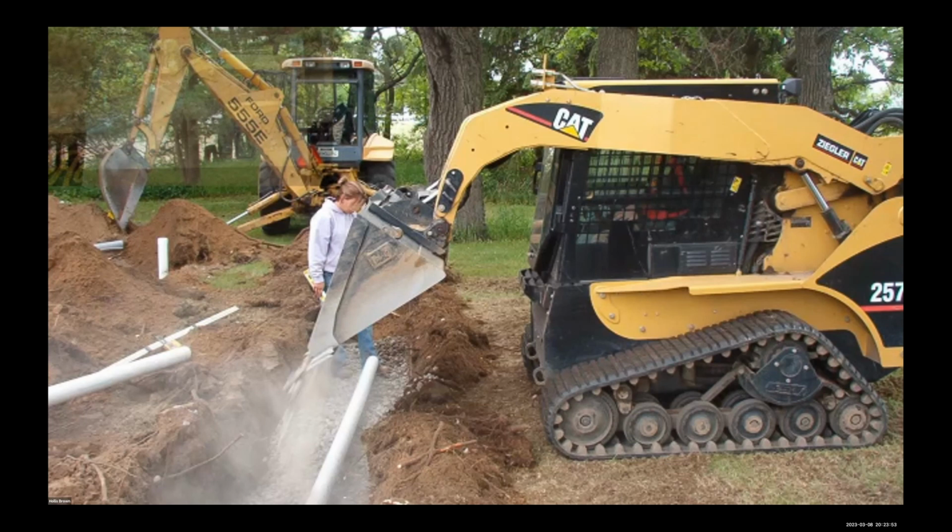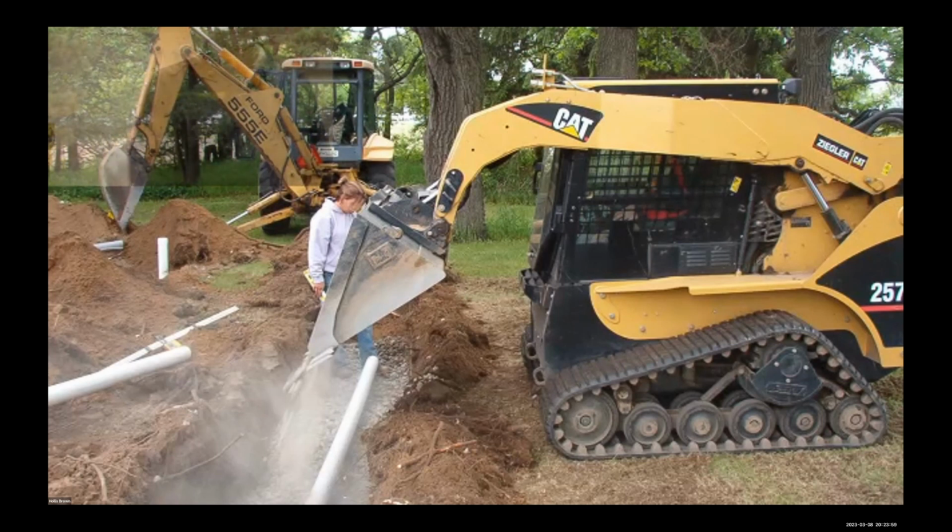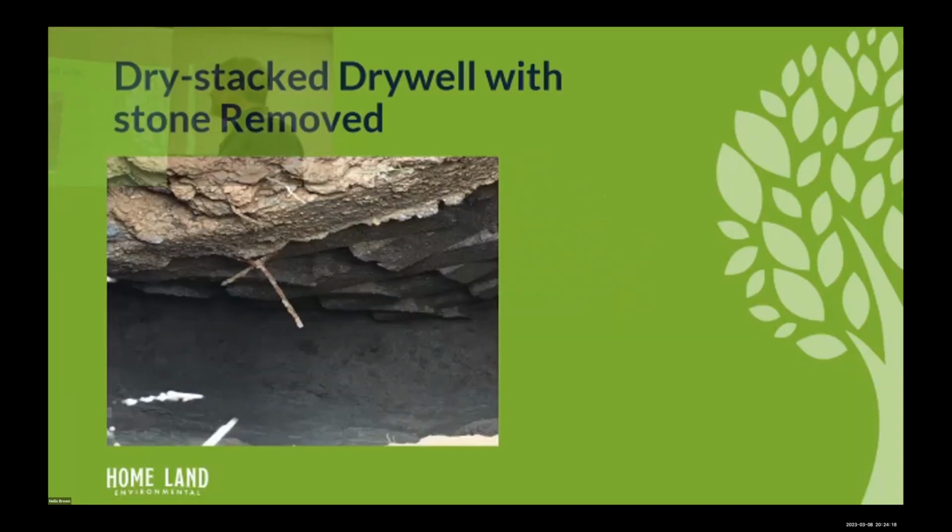Just a picture of some stone. They use number 2 size limestone, I believe, really big. And the pipe sits on top. That pipe has perforations in the bottom of it, right? So the water that leaves the D-box first goes through a hole in the pipe, goes through that 4, 5, 6 feet of stone, and then into the soil, which filters the water again, right? Septic tank filters it, the stone filters it, and the soil filters it. I mentioned dry wells.